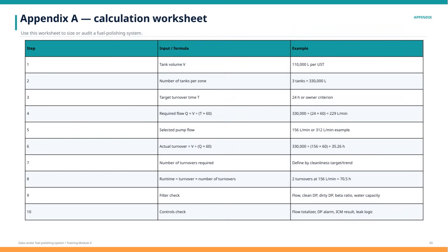Using the actual pump flow, we determine the actual turnover time by dividing the total volume by the product of the pump flow and minutes per hour. For instance, with 156 liters per minute, the turnover is about 35.26 hours. The number of turnovers required depends on the cleanliness target or trend of the system. Multiplying the turnover time by the number of turnovers gives us the total runtime. In the example, 2 turnovers at 156 liters per minute equals 70.5 hours.